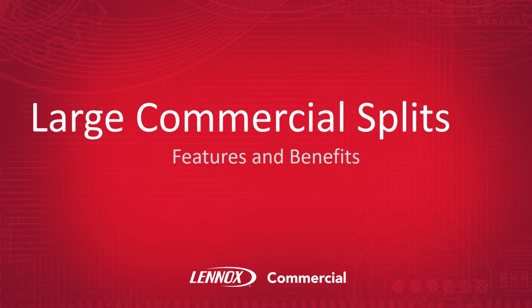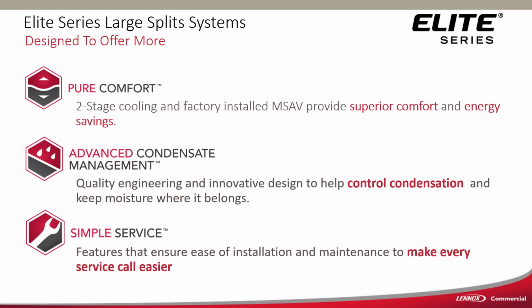Large commercial split systems. This is our Elite Series commercial split system with the ELS condenser and the ELA air handler. 2 stages of cooling and multiple stage air volume is standard on these, period. When you order an ELA air handler, it will come with MSAV. And when you order an ELS condensing unit, it will have 2 stages of cooling, not necessarily 2 compressors, but 2 stages. It has the enhanced condensate management system. We've engineered this in there to help keep the moisture where it's supposed to be and prevent condensate leaks. And this is set up very easy to service and easy to work on.